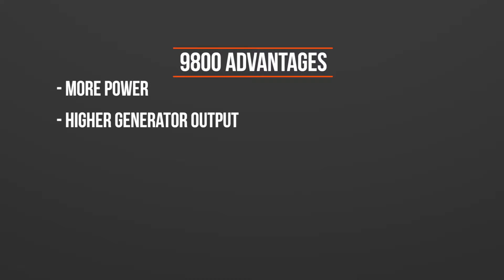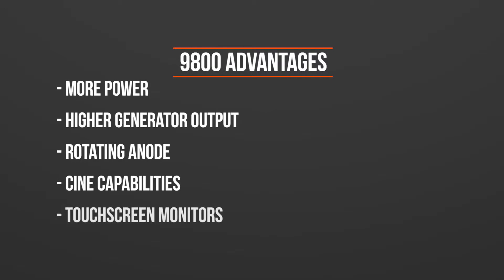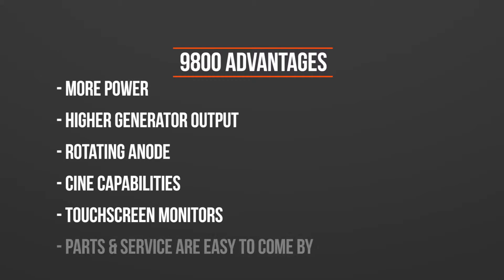The 9800 has a higher generator output, has a rotating anode for much greater heat capacity with CINE capabilities, has touchscreen monitors, and parts and service are easy to come by.